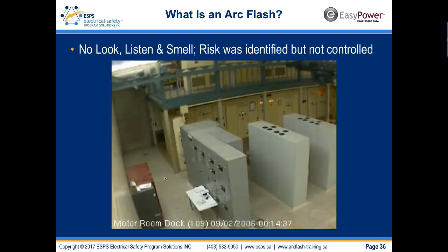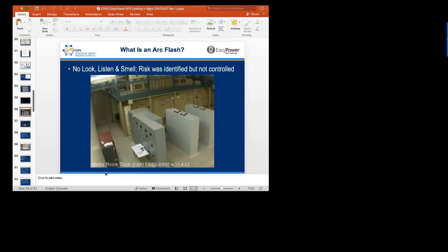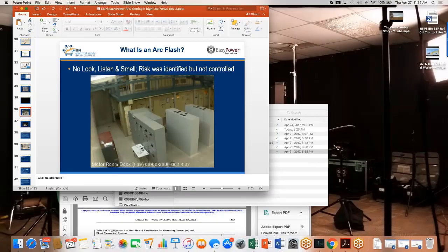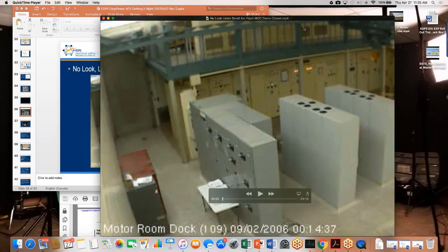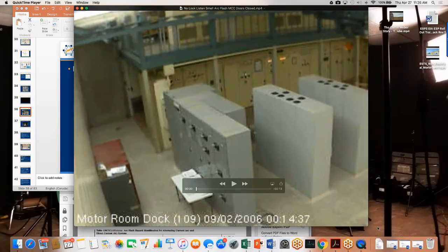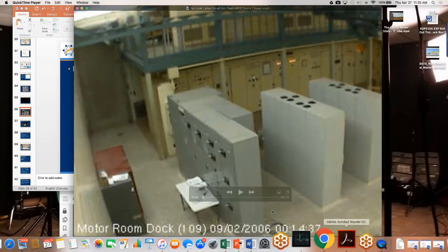I call it no look, listen, and smell. And again, when I show these videos, it's all about the risk. So what was the risk to the worker here? In this case, the worker did not recognize an abnormal condition on energized electrical equipment, and you're going to see them exposed to an arc flash.